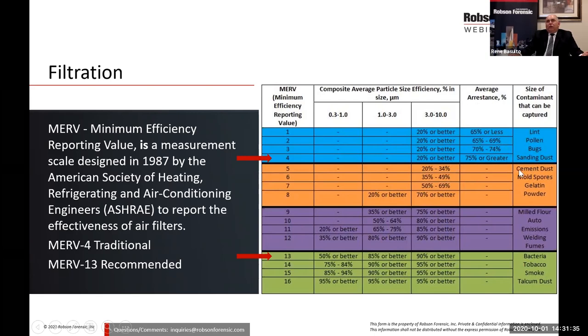You'll see the efficiencies out here and what they'll block. The MERV 4 will take care of lint, pollen, bugs, sawdust, all the larger materials. But in the lower size of particles, you see that it's very ineffective and not effective at all. So the MERV 13 is what's now being recommended. You'll see that it's a much higher efficiency.